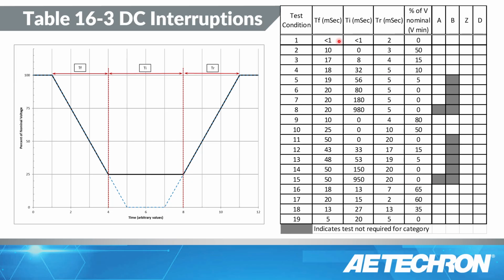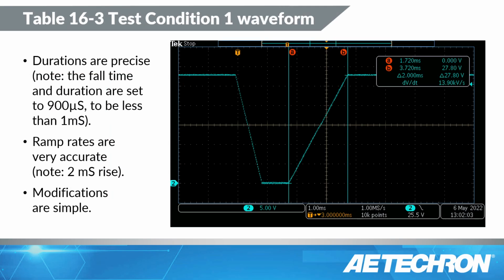Let me look at this first one in particular, test condition 1. It says you have to drop in less than 1 millisecond, and then you have to dwell at that voltage for less than 1 millisecond, and then you have to rise from that 0 volts, as it turns out, up to full level in 2 milliseconds. Well, this can be a bit of a challenge if you have to try to manipulate these voltage waveforms very specifically. This is where the AE Techron 3301 excels.